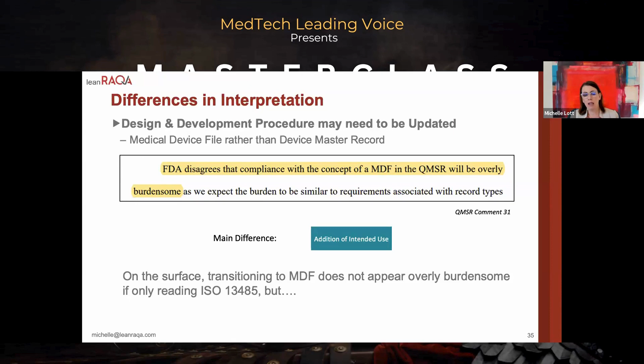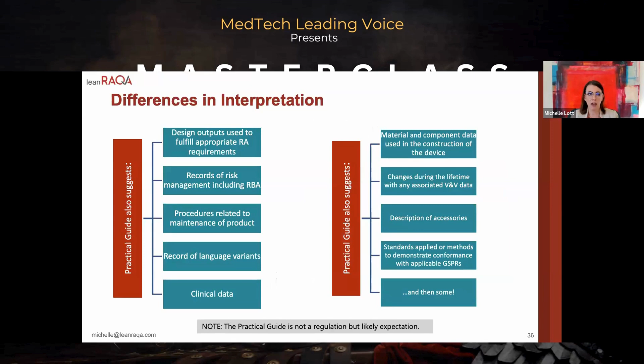So on the surface, if you read 13485 alone, the concept of MDF does not appear to be overly burdensome, because really the main difference is the addition of including the intended use in the MDF document. But like we talked about, you need to understand the concepts that are embodied in the practical guide. In that case, you also need to consider all of these things in the contents for your medical device plus some. So it gets really lengthy and can be really tedious to develop a medical device file, depending on how deep you go into the interpretation of the practical guide.